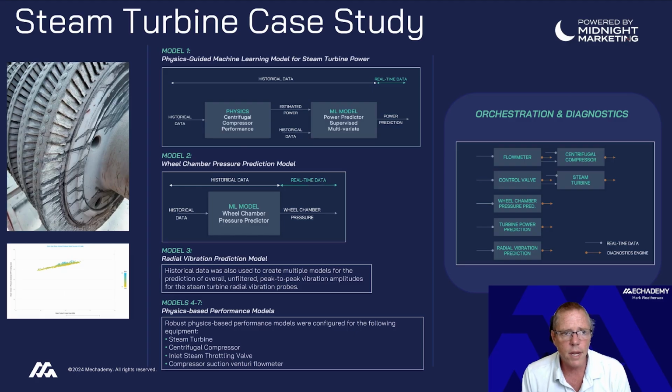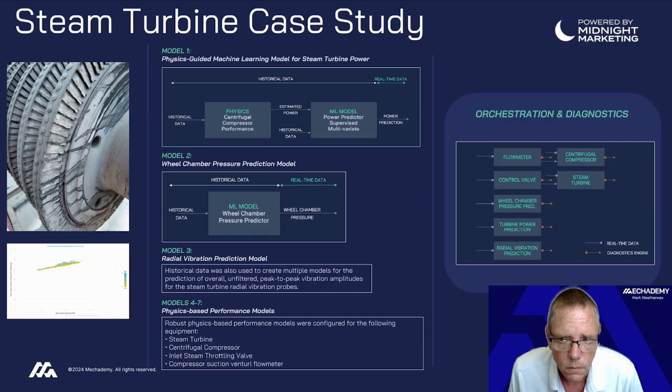So let's get to the case studies. The other case study that I wanted to show, I'm showing it for a different reason. This is a steam turbine problem, and this was actually driving a hydrogen compressor, and the hydrogen compressor was having mole weight swings, going from pure nitrogen at startup to almost pure hydrogen with some heavy tails in it and stuff.